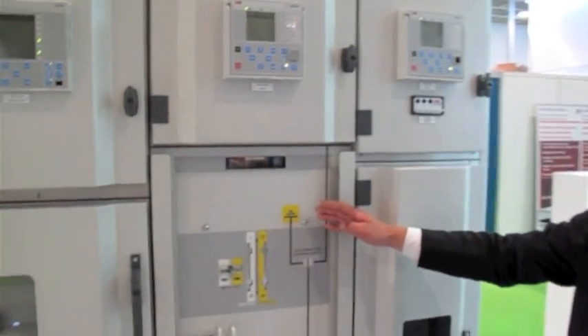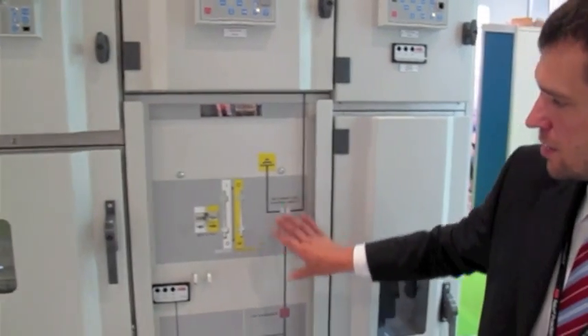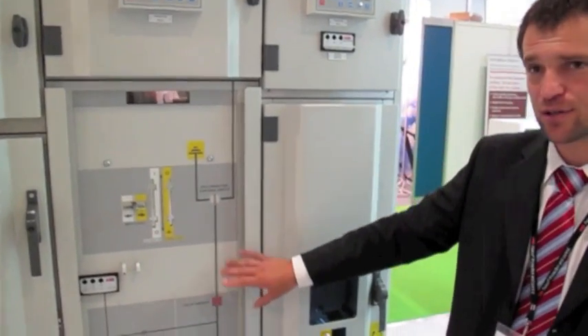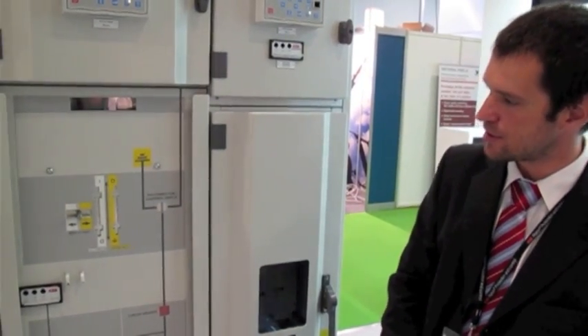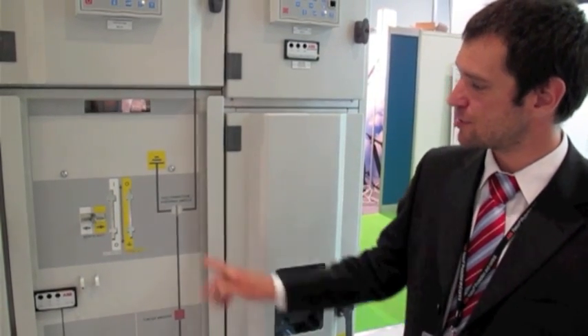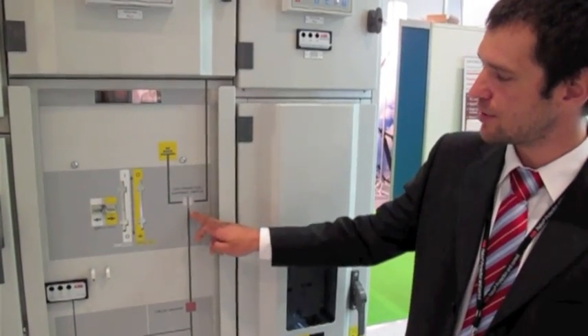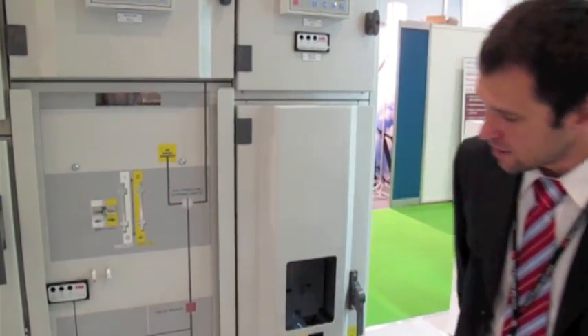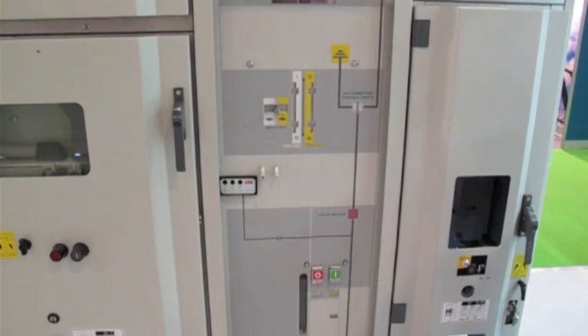The second cubicle is different. As you can see, there are not many doors because this 500R cubicle is a fixed pattern — it means the circuit breaker is integrated into the cubicle. Also, this cubicle has no earthing switch. There are only three positions of the disconnector switch: connected to the bus bars, isolated position, and earthing position connected to the earthing bar. Everything else is done by the circuit breaker, which is placed in this part.